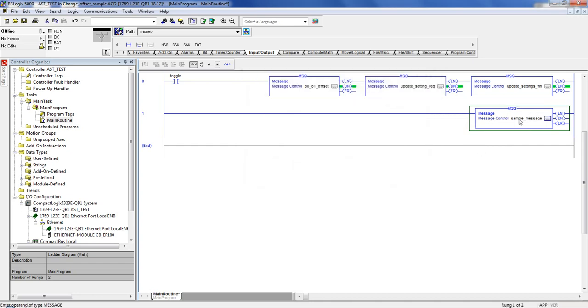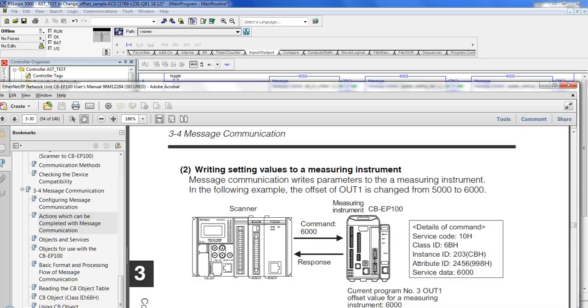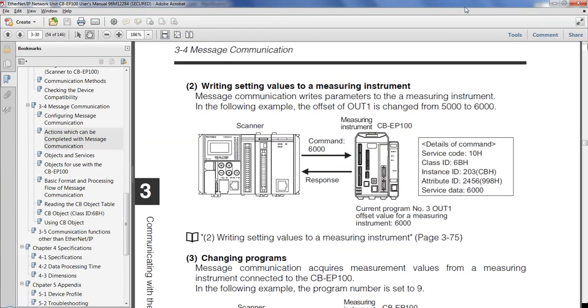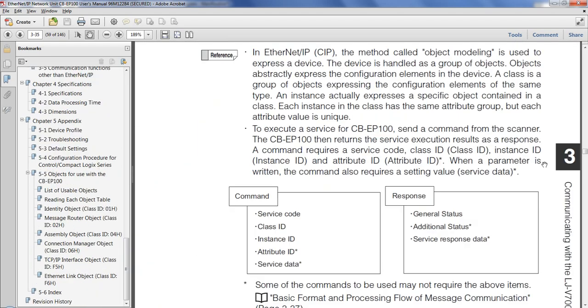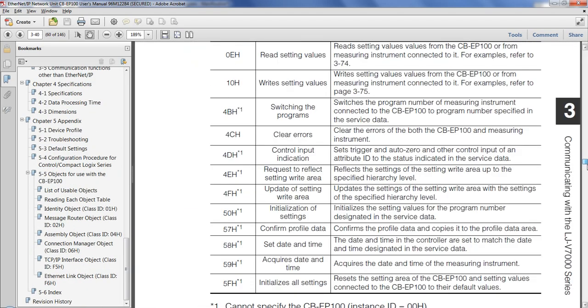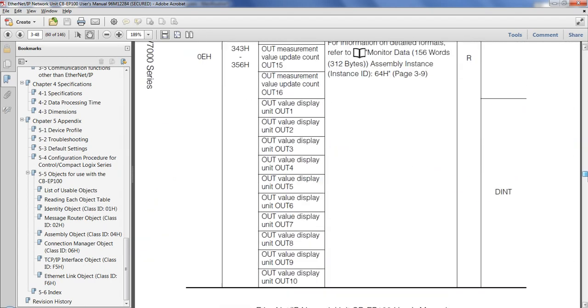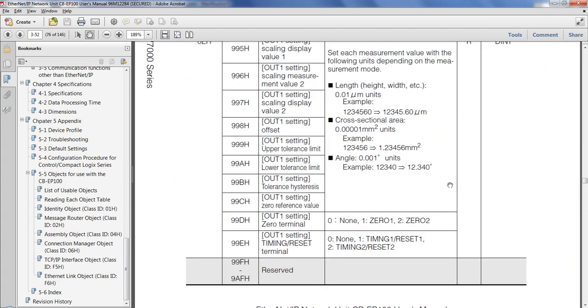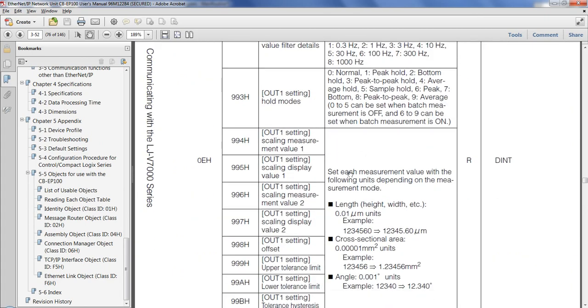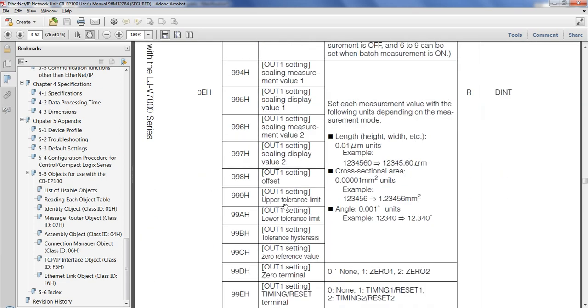So that's all it takes to create a message. I've already done a couple of them here. So I'm going to go ahead and delete this one as we don't really need it. One thing that we saw earlier, so here, looking in the manual, we have the attribute IDs, device ID, or service code, and class ID. Those are pretty much defined. So just know for writing data, it's 10. Class ID is always going to be 6B. Instance is going to be your program. Attribute is going to be where to write it to. And just so I can demonstrate that really quickly, we saw that that one was 998. So we scroll through here. Out1. If you wanted to change out1 offset data, 998. That's where we got it from. So everything is laid out, attribute ID, inside this manual already.